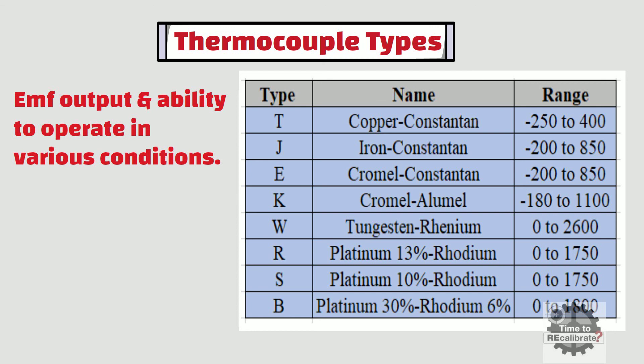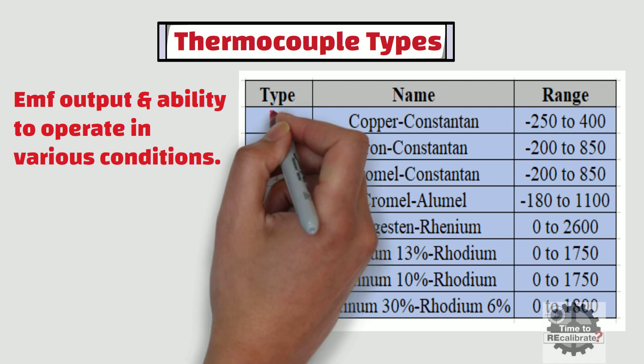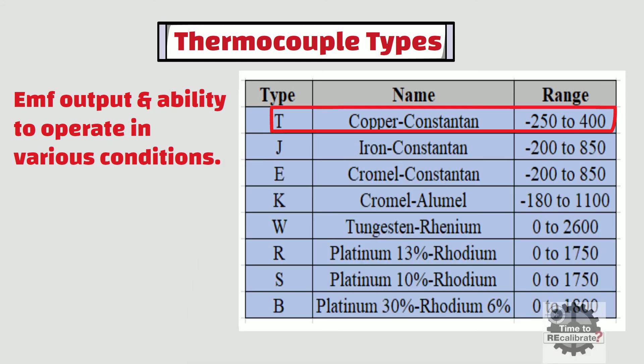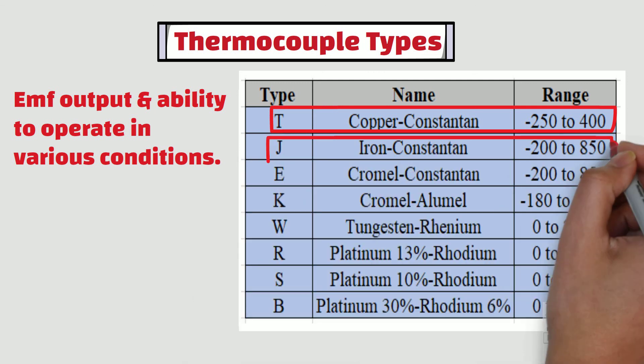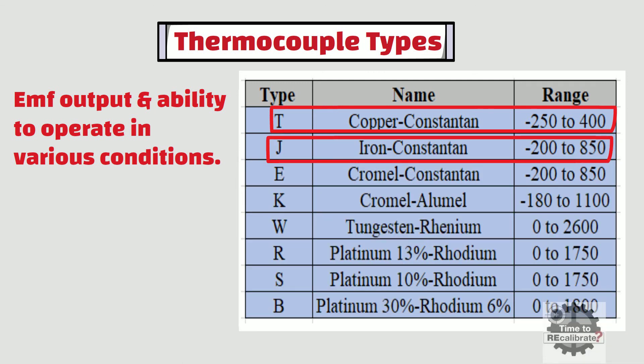As you can see from the chart, particular thermocouples are more suited to specific applications and temperature ranges than others. For example, type T thermocouple is used in applications up to 400 degrees Celsius. Similarly, the type J or iron and constantan thermocouple is the most widely used. It is used in applications up to 850 degrees Celsius.